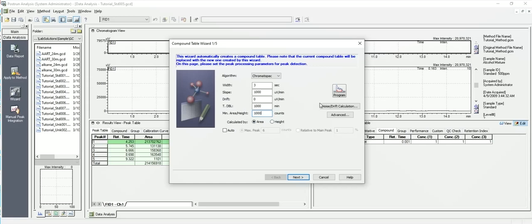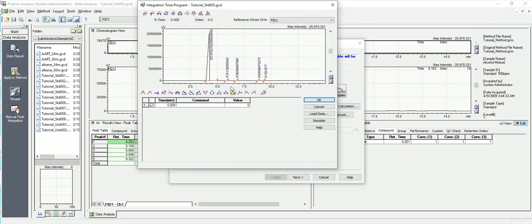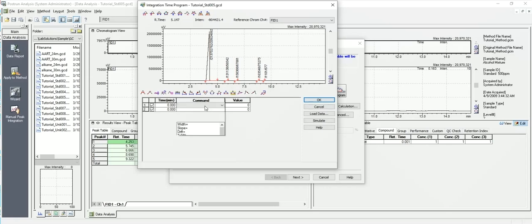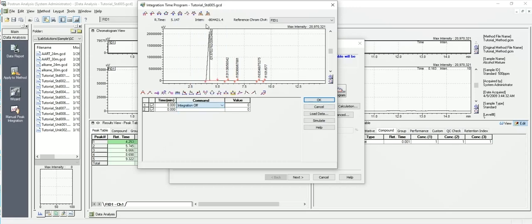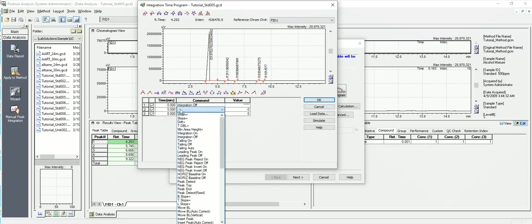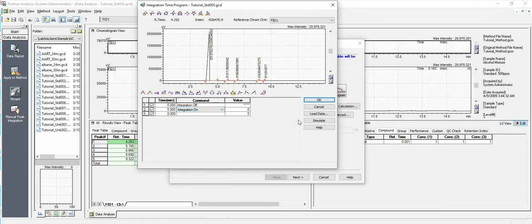Something else we can use over here if I choose to is in a program here. Since I know that this peak here, and also this is a good example to see what fronting looks like, but it's a solvent you expect at the front. So at T zero here what I may do is turn the integration off, then at five minutes I'm going to turn my integration on. Simulate it and you can see that's exactly what we want. So I'm going to leave that there.